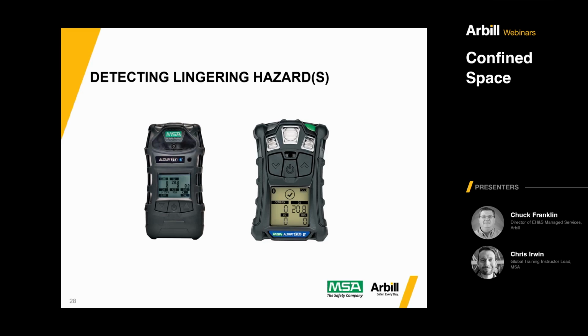And one brief comment I'll make is without the proper technology, it isn't okay to just attach this to a string and lower it into the space to do your testing from the outside. I really need to caution you, whichever device you're using, you want to make sure you're doing it the way the manufacturer specifies, just to know that you're not going to run into any kind of issues and you're doing it the way they want you to. Technically, both of these devices could be used either way, but as I mentioned, I think they each have a strong suit. You don't need to have both. You could have one or the other. But if you've got the capability of having a 5X on the outside and 4XRs on the workers in the space, even better.